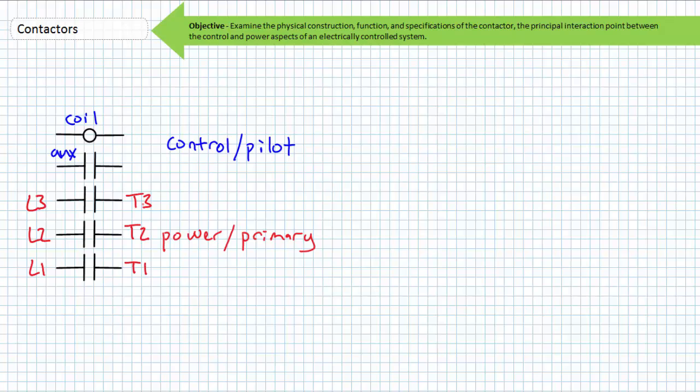This is a 3-pole contactor that would be used to make or break connection to an industrial motor supplied by either 208 volt or 480 volt 3-phase AC as representative examples. The L side is sometimes known as the line side. The T side is sometimes known as the load side. When closed by the low voltage control signal supplied to the coil, the passage from line to load is a conduit for muscle power.